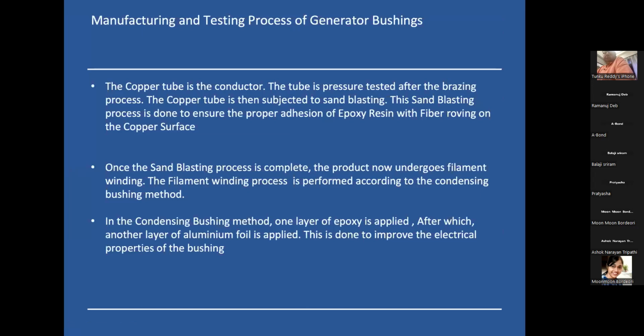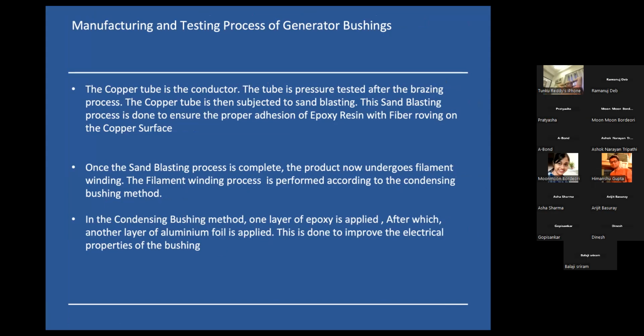So now the first step is the brazing process. The copper tube is the main conductor in the generator bushing. It has to first be subjected to sandblasting. Now, why is sandblasting done? It is to ensure proper adhesion of the epoxy resin with the fiber roving on the copper surface. Once the sandblasting is complete, we can start the filament winding process.